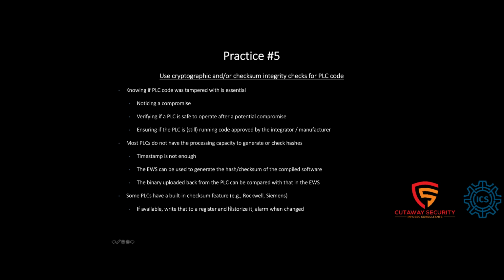But of course, some modern PLCs have a built-in checksum feature. If there is one, in these examples Rockwell or Siemens, use it and then write that to a register so that you can historize it and alarm when changed. So let's say there's some testing or commissioning going on, there's an open permit, so the engineer is playing with the logic and downloading to the controller. By all means, the operator can ignore it. But in the middle of the night, nobody should be touching the PLC, and if you have this alarm, the checksum on a PLC changed, by all means you have to pay attention to it, because somebody could be manipulating that PLC code.